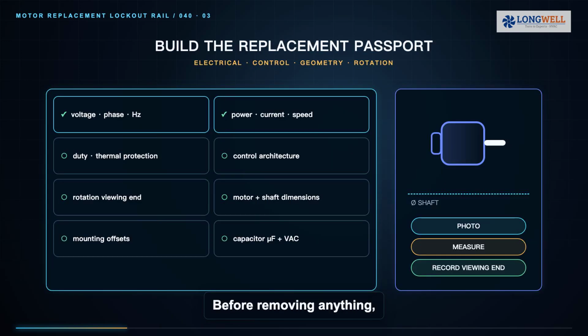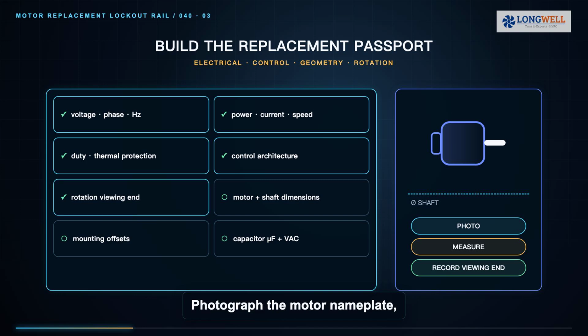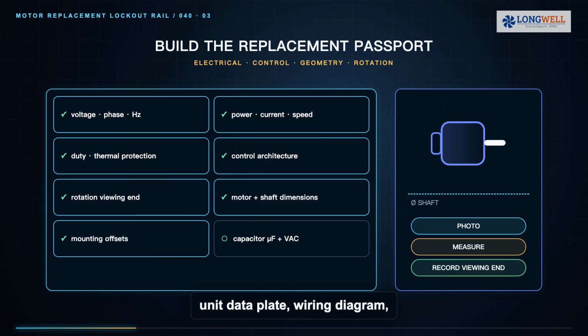Before removing anything, build a replacement passport. Photograph the motor nameplate, unit data plate, wiring diagram, connector positions, and the complete blower assembly. Record voltage, phase, frequency, rated power or horsepower, full load current, rated speed, duty, thermal protection, frame and mounting style. Measure motor diameter, shaft diameter, usable shaft length, bracket offsets, and connector clearance. Record rotation from the viewing direction defined by the manufacturer.